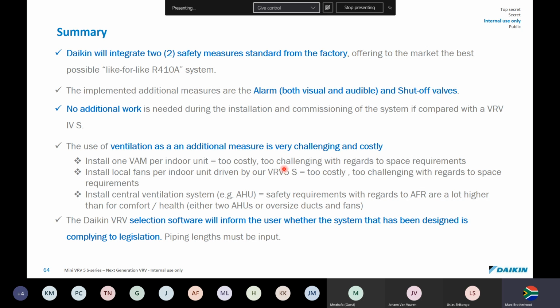But if you have 20 indoor, well, you're not going to have 20 indoor units. It's a mini VRV. You might have 3 indoor units. We can supply a voltage output, but then you're going to watch what size fans you use. So you need to pull them in with relays, because they're going to pull too much power and they're going to blow the board. Or you could install a central ventilation system, for example, an air handling unit.